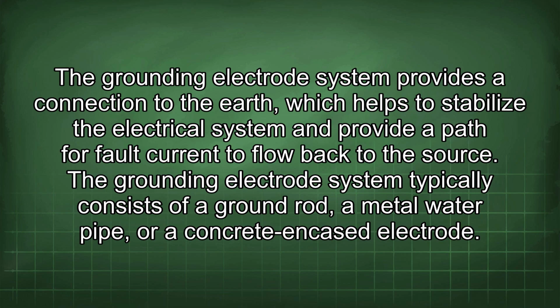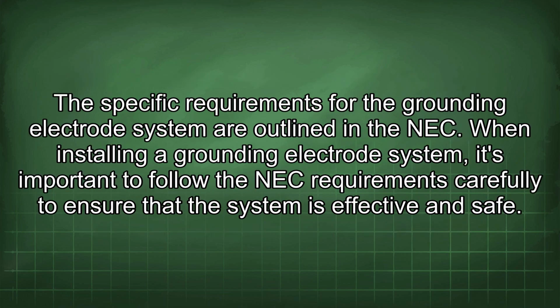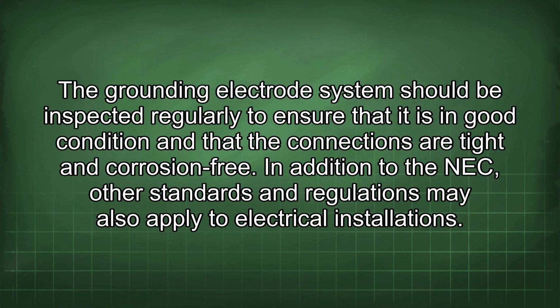The grounding electrode system typically consists of a ground rod, a metal water pipe, or a concrete encased electrode. The specific requirements for the grounding electrode system are outlined in the NEC. When installing a grounding electrode system, it's important to follow the NEC requirements carefully to ensure that the system is effective and safe. The grounding electrode system should be inspected regularly to ensure that it is in good condition and that the connections are tight and corrosion-free.